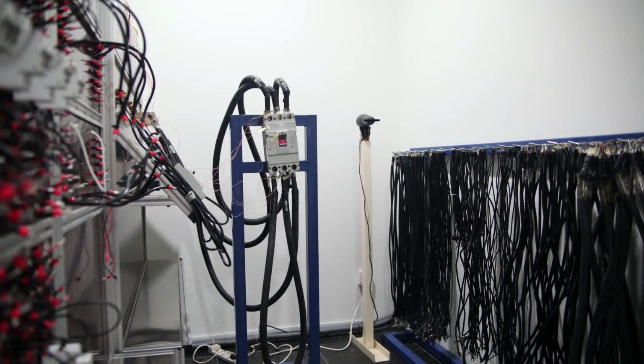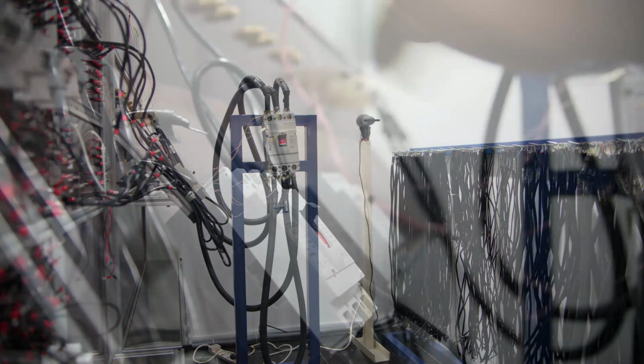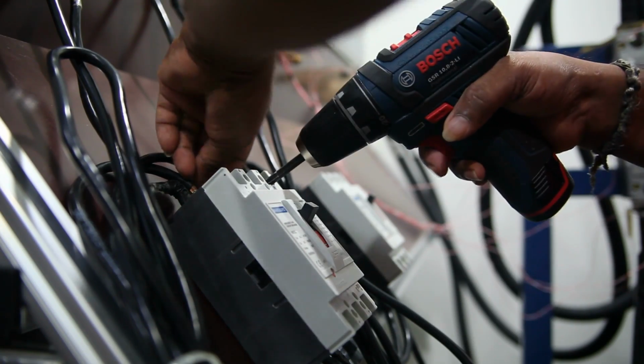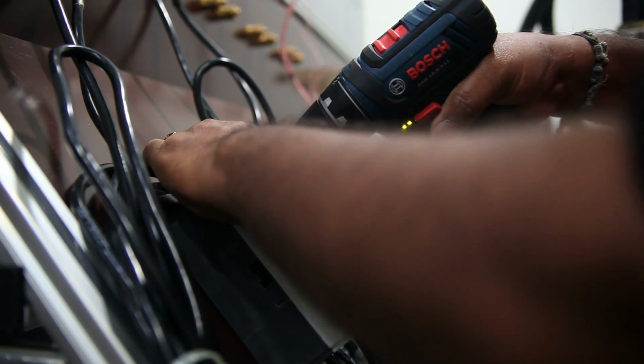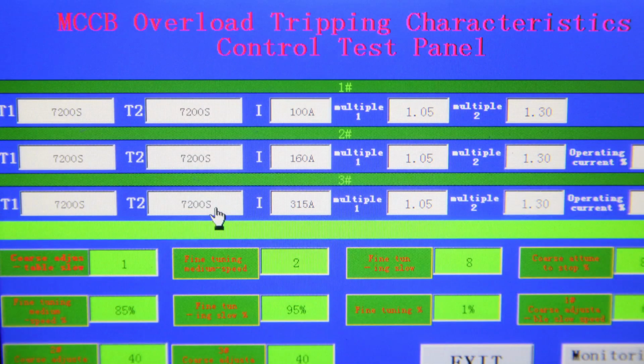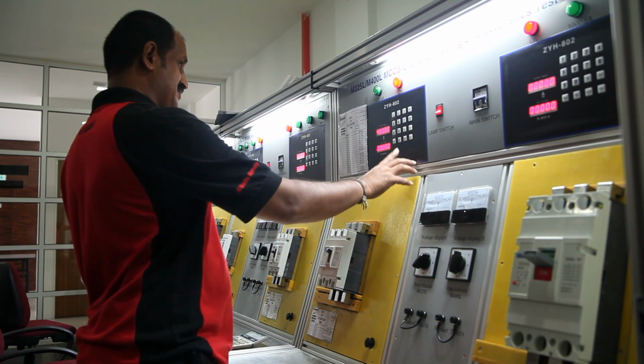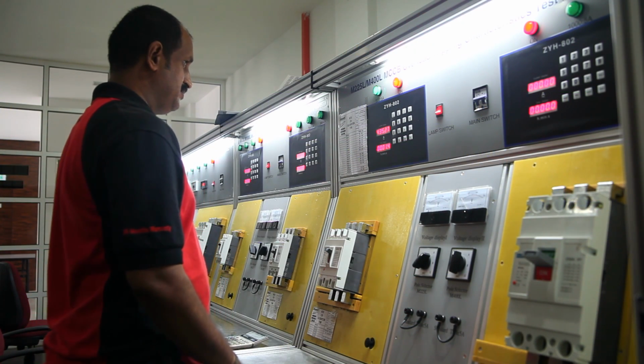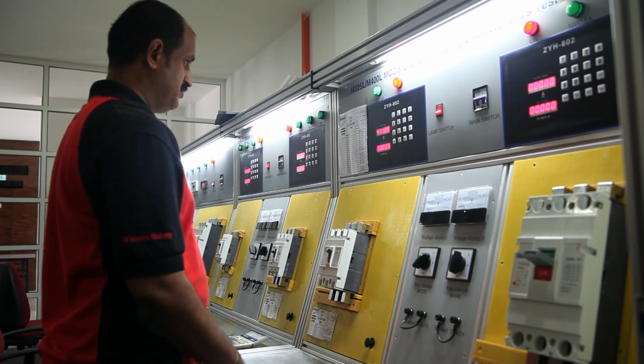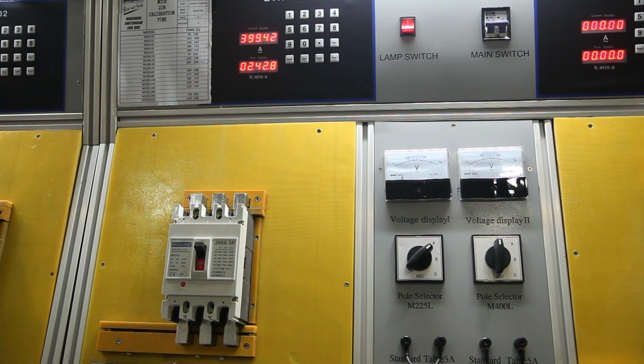MCCBs marked 40 degrees Celsius are tested in a temperature-controlled room. MCCBs are also to be verified for functions against the time current characteristics curve provided. Current of 2 times is injected to verify if tripping time is within the curve. Tripping outside the characteristic curves denotes non-compliance.